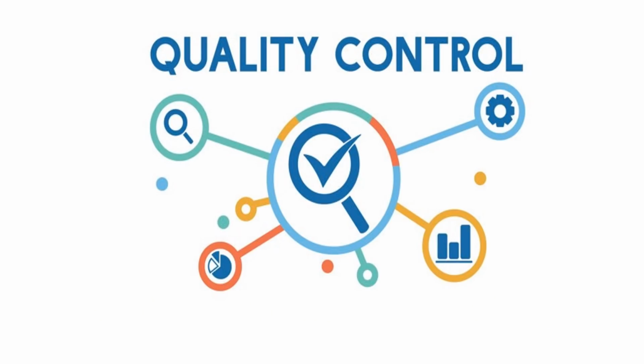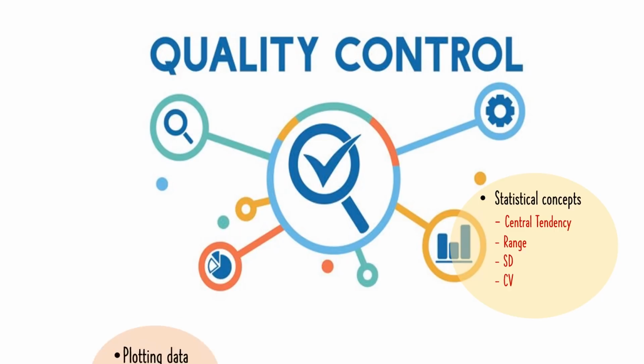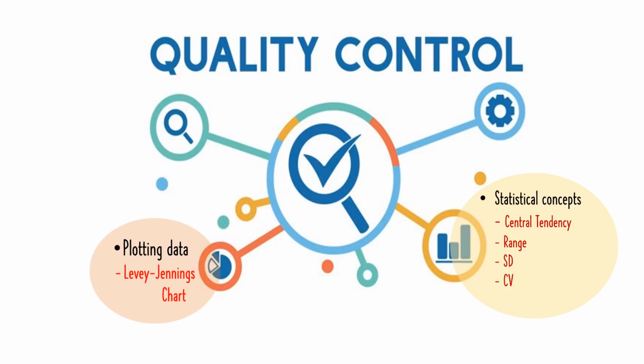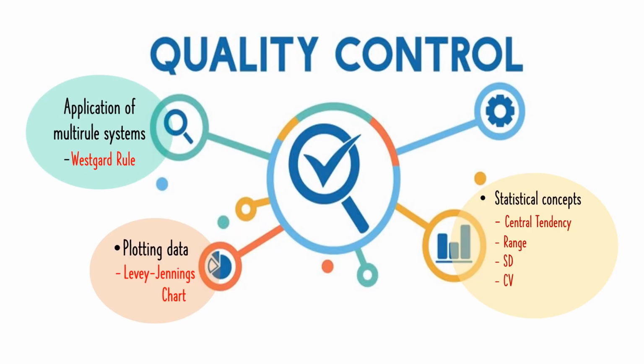As I have mentioned before, quality control is measured by statistical approaches. So the methods or concepts applied in measuring quality control include central tendency, the range, getting the standard deviation, as well as the coefficient of variation. And then once we have the values, we are going to plot the data using the Levey-Jennings chart. Based on the Levey-Jennings chart, we are able to identify errors, if there are any trends and shifts in the results of our control samples, and apply the multi-rule systems or the Westgard rules.